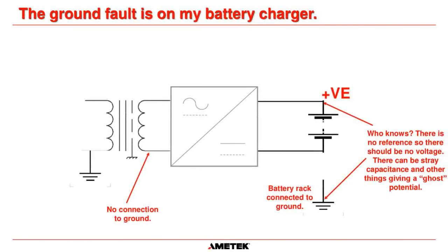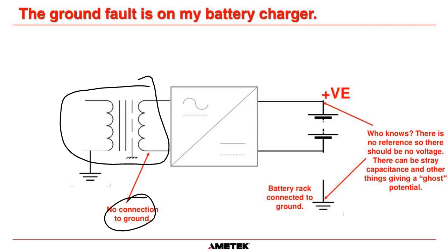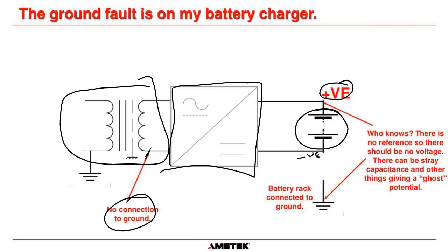So, once again, we have that exact same circuit here. There is no connection to ground on the secondary of this transformer. And now all we've done is put a charger here. So now we have our positive here, our negative here, and our battery at this point. If you measure from positive to ground, what is the voltage going to be? Who knows? There is no reference, so there should be no voltage. Once again, there can be stray capacitance and other things that give a ghost potential.